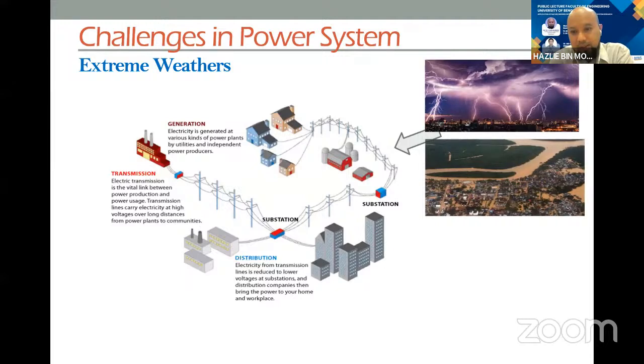And then floods. I think Indonesia or Malaysia have the same problems. This is a photo of a flood that happened in 2014 in Kelantan. In Malaysia we have different states, so the whole state of Kelantan was flooded that year. This is the worst flood in 100 years in Malaysia. Because when flooding happens, many of the substations will be flooded, and the water will enter the substation, so it will need to be tripped off for the safety of the system. If not, a flashover will happen.